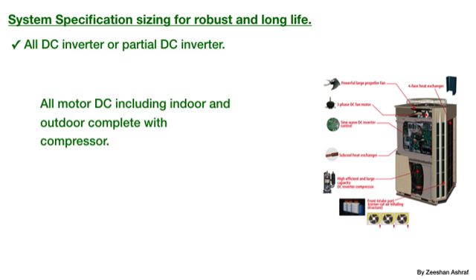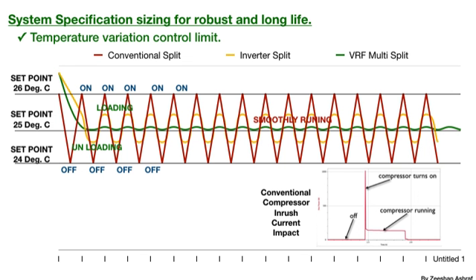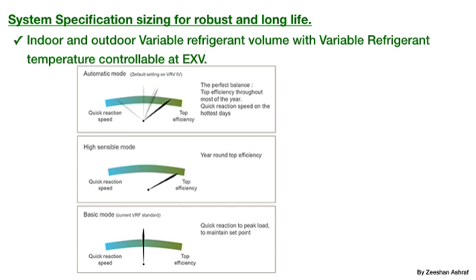Make sure the unit is full DC inverter, with all motors DC inverter driven. With a single inverter driven unit, the temperature control limit is minimized to plus and minus 1 degree centigrade. But with the multi-split unit, that is the VRF unit, this limit is minimized to plus and minus 0.2 degrees centigrade, and due to load shifting from room to room there are further advantages. Due to the central system, this difference is almost zero.